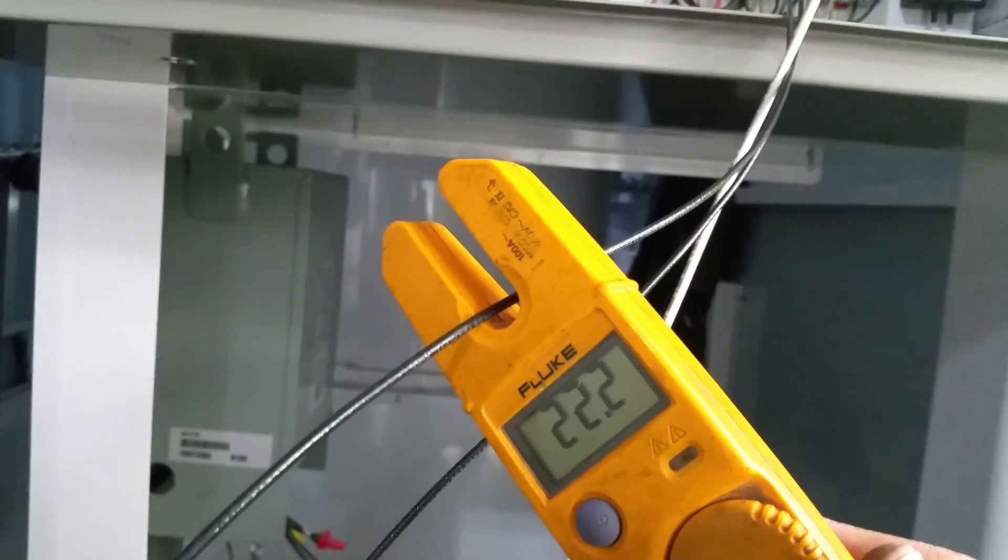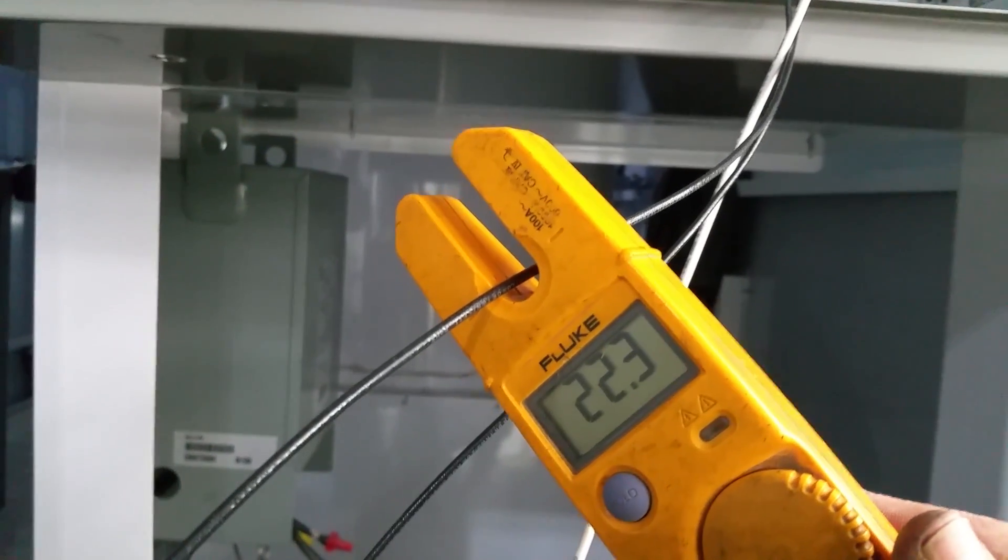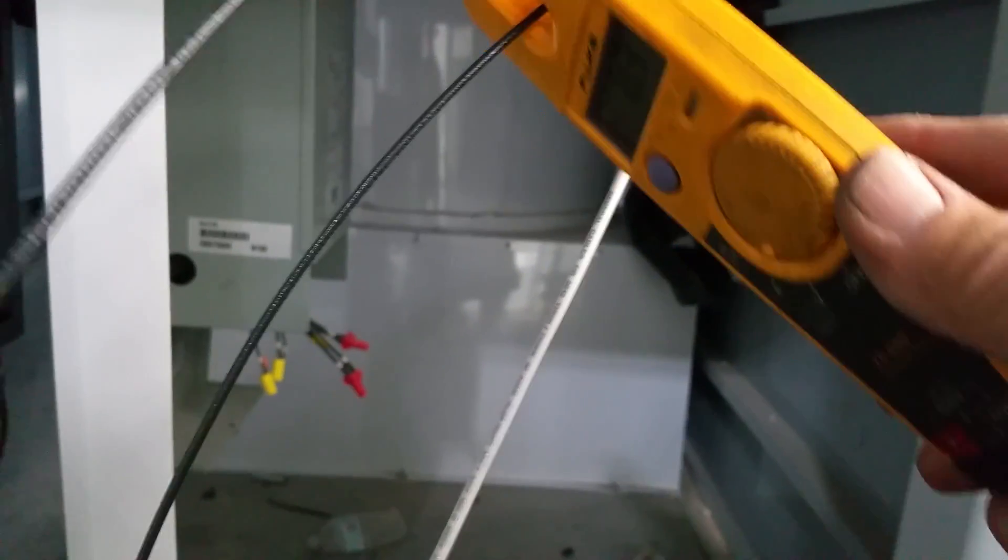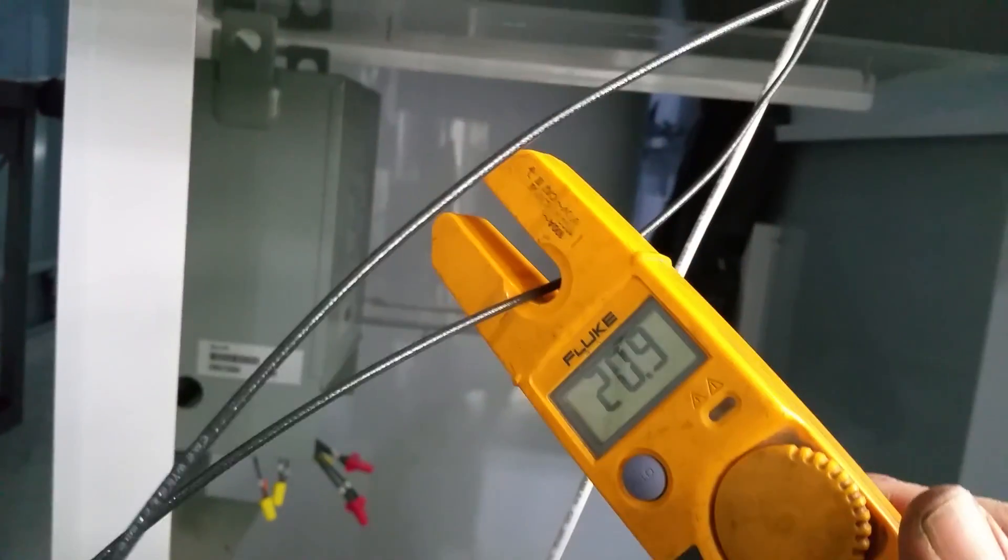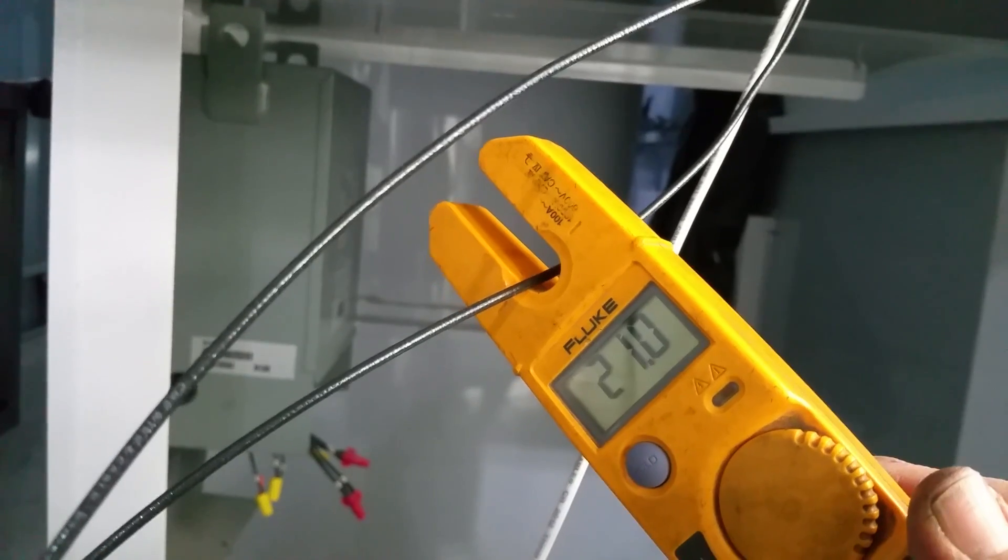Now we're going to fire the second half and we're going to find out what happens to that neutral. Here we've got 22 on one hotleg and we've got 20 on the other hotleg or 21 on the other hotleg.